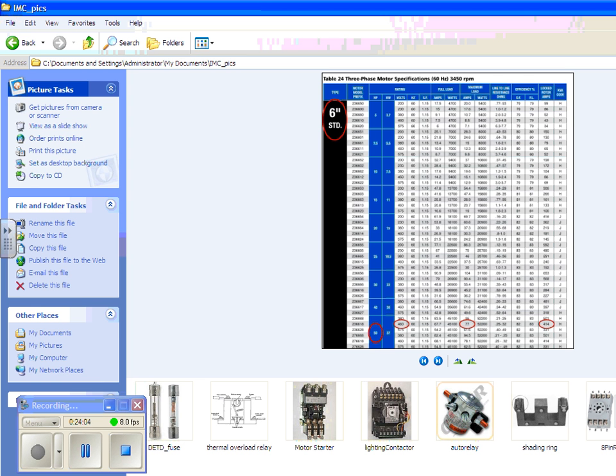In other words, European. Now, there is a major difference between the 2. NEMA is American made, and they're very heavy duty. They will very seldom burn up. If you size them correctly, generally speaking, they will live forever. Now, I shouldn't disparage using an IEC starter, but I'm going to, in spite of the fact that that's probably not the right thing to do. But my experience in the field has shown that even if you select the exact right IEC starter, it may not live for very long. They're built very precisely, and if the very slightest overload is in it for any long period of time, they have a tendency to not work very well.